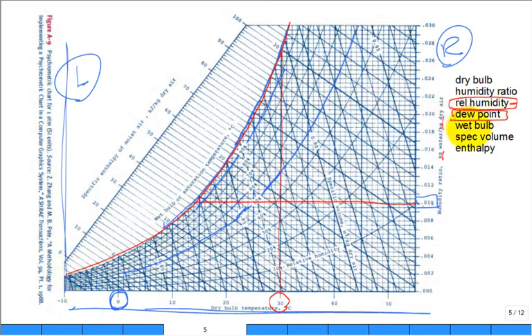Now, we talk about dew point. Let's go out here and do an example. Let's pick 30 degrees and 0.01 humidity ratio, just like that. So, here is my condition of the moist air. Can you tell me roughly what the relative humidity is closest to whatever percent? A little bit below 40%, 38%. Yeah, let's call it 38%. Can you tell me what is the dew point temperature for that air? 30 degrees C is the dry bulb. 0.010 is the humidity ratio. It's a little less than 40% relative humidity. What is the dew point temperature? That's a hard question.